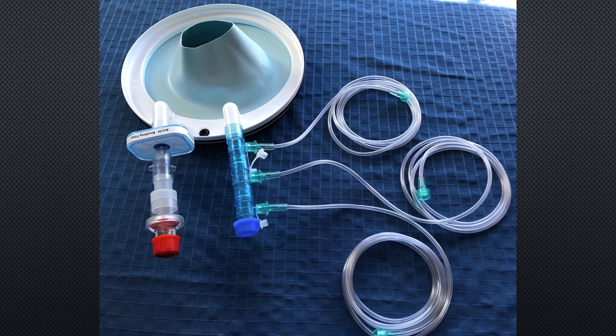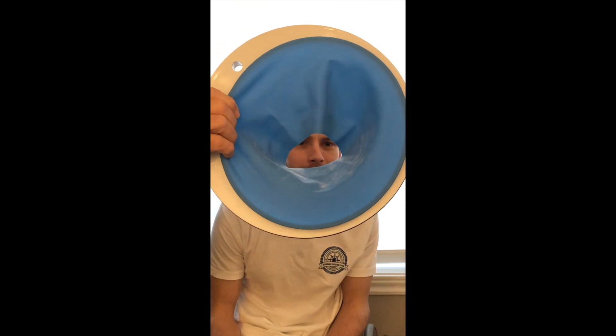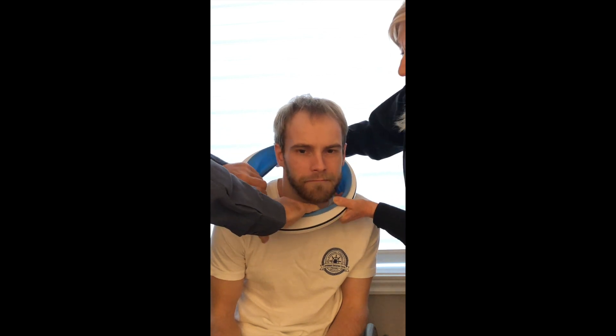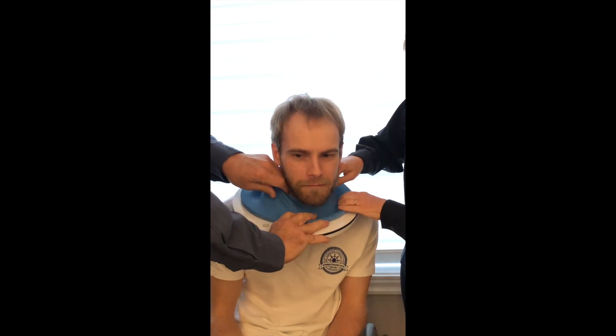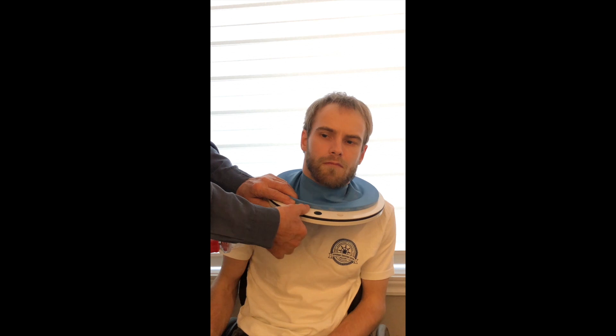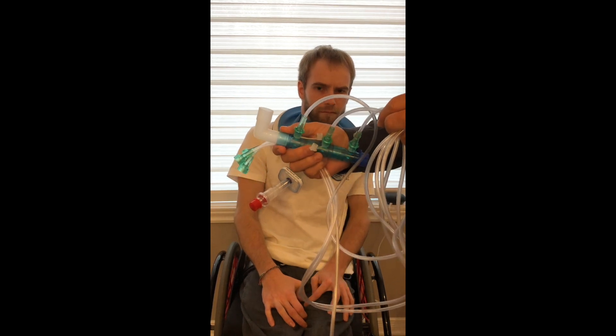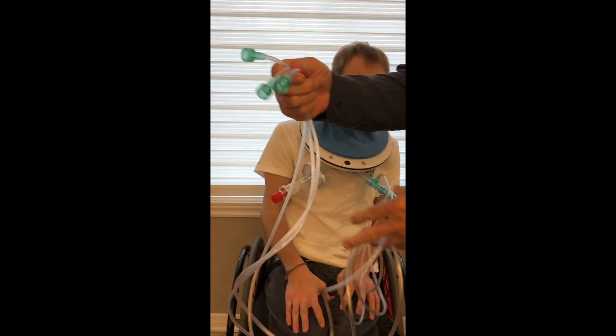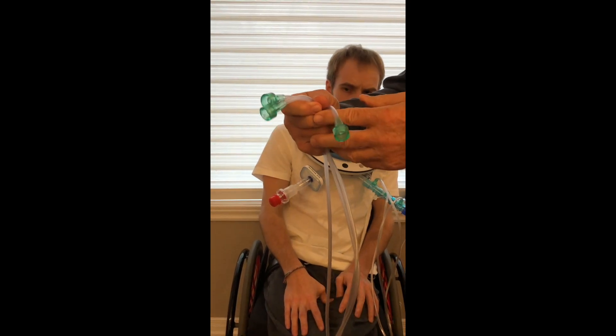Here you see the oxygen treatment hood assembly ring with both assemblies attached. Once the neck seal has been trimmed to the size of the patient's neck, it requires two individuals to lower it around the patient's head and place it comfortably on the neck. Once the hood base is in place, you can attach the exhaust assembly to one side as shown in the video. The next step is to attach the oxygen assembly, which has three lines connected to regulators from the wall — two to oxygen, one to medical air.